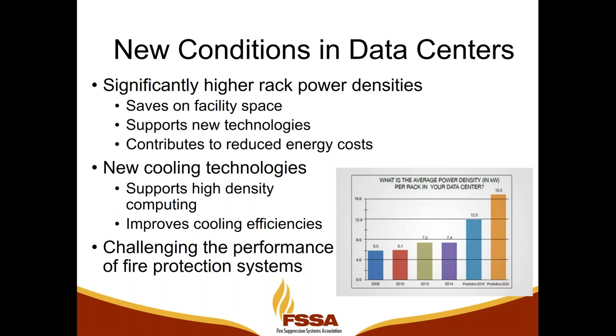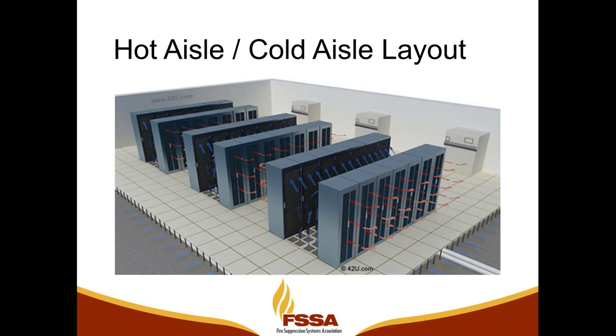And to cool that down, there are new strategies for air handling in data centers. And ultimately, it's that new cooling strategy that's in place in many facilities that is challenging the performance of our fire protection systems. So when we look at a data center, we often talk about the layout of the racks. And this used to be not common. Now it's very common to have a hot aisle, cold aisle arrangement.